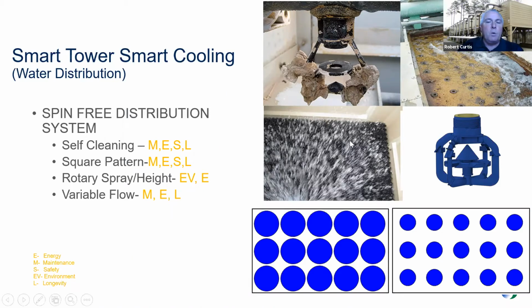This is an actual picture of our distribution system, shown here in a corner, where you can see it forms a square pattern that Tower Tech developed with this nozzle, distributing water in a square pattern. Traditional nozzles, by contrast, create round circular patterns with void areas, which are less efficient and have more potential maintenance issues. Tower Tech solved that with the square pattern.